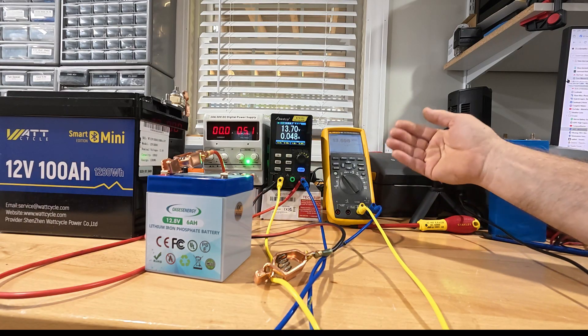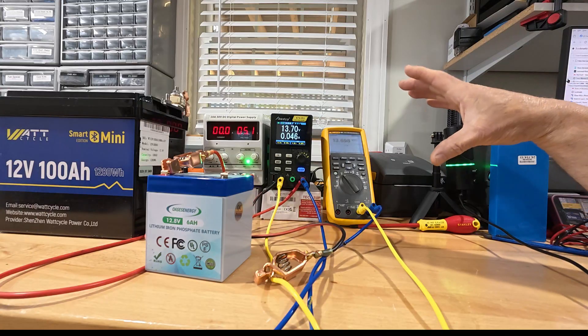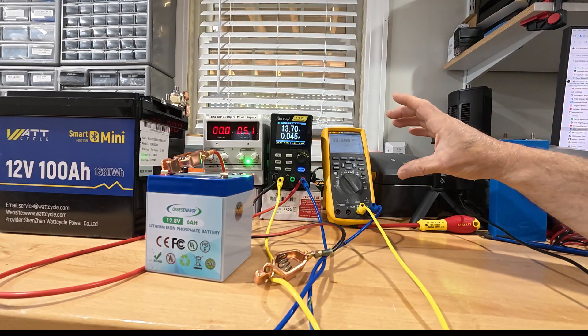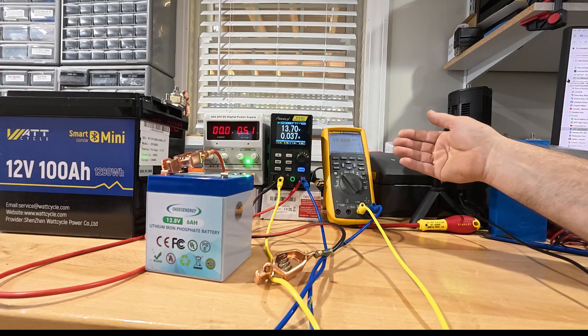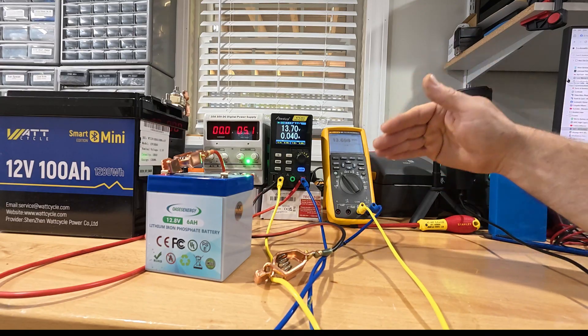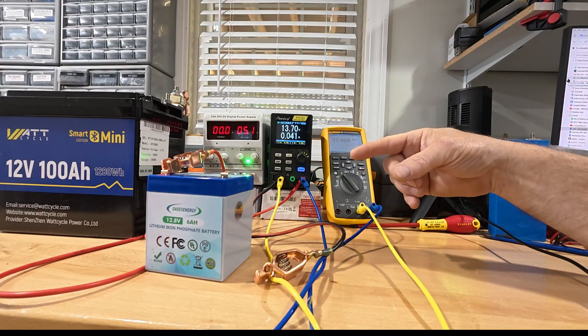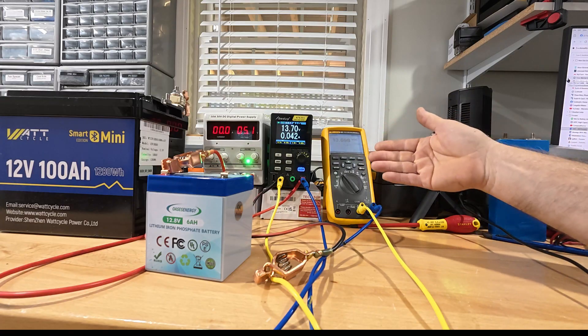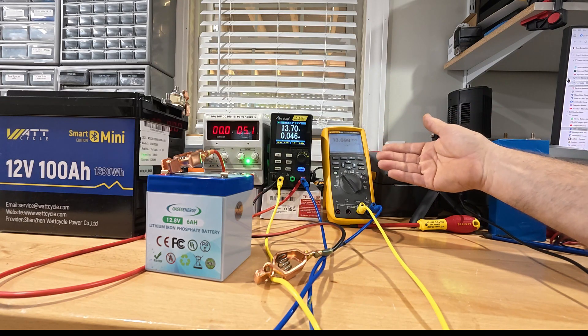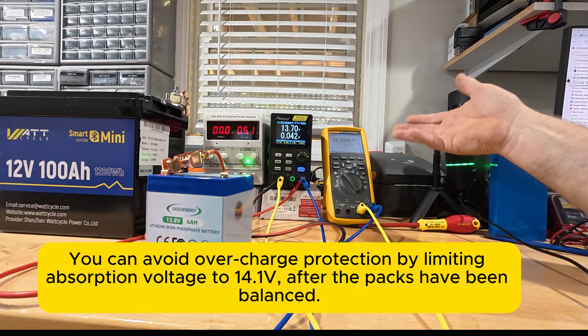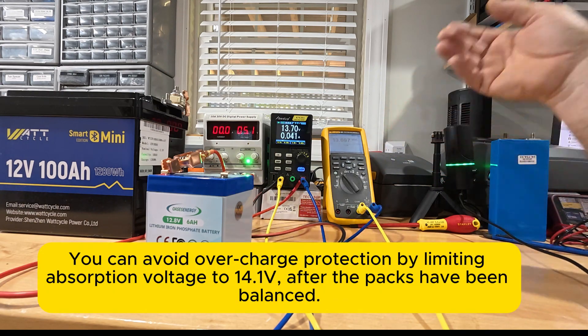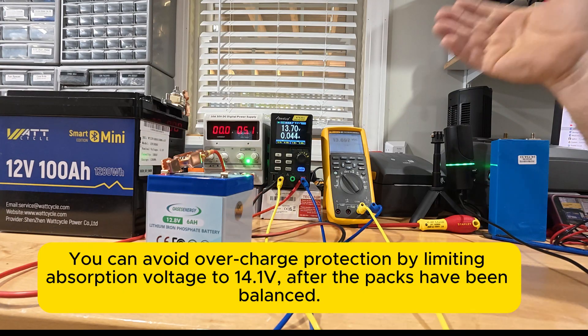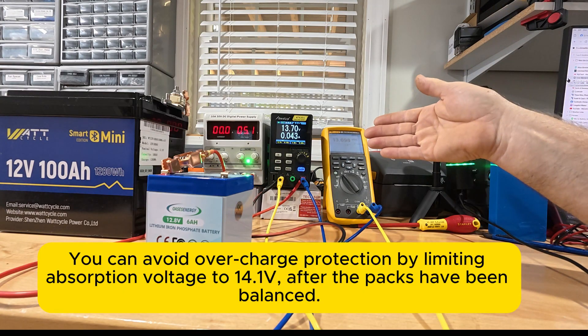And now that battery that shut off is not going to re-engage until a certain voltage because there's hysteresis built into the BMS. So once you start discharging, the other battery that was at a higher state of charge because it was better balanced, it ends up doing all the work until you get down to a voltage where the second battery kicks in. So if you start with perfectly balanced batteries or as close to it as you can get, you'll have much less of a chance of that. The other thing that you can do, of course, is you can lower your charge voltage, but you never want to lower your charge voltage below where your balancing voltage is.